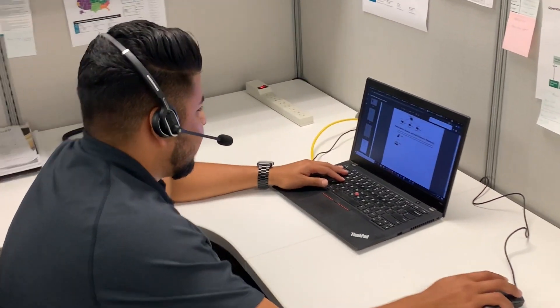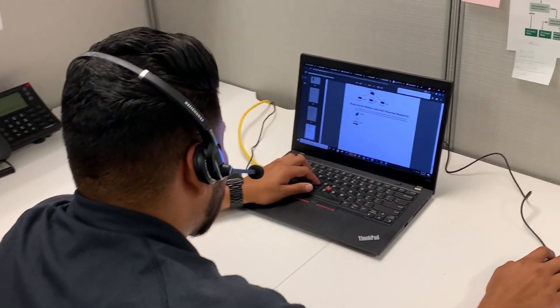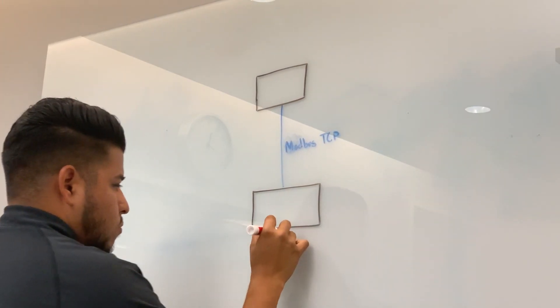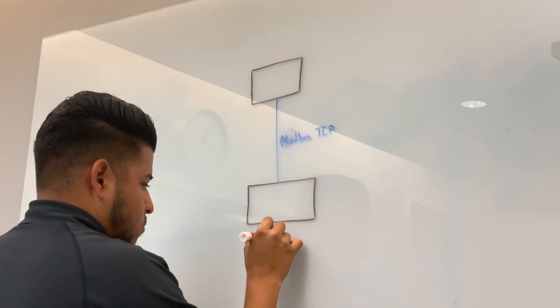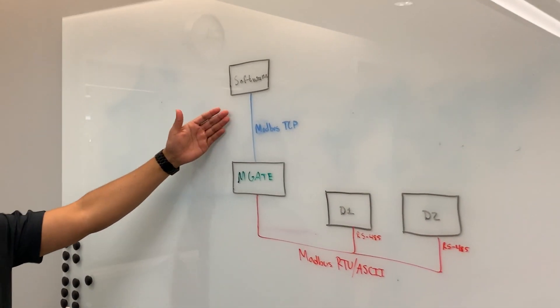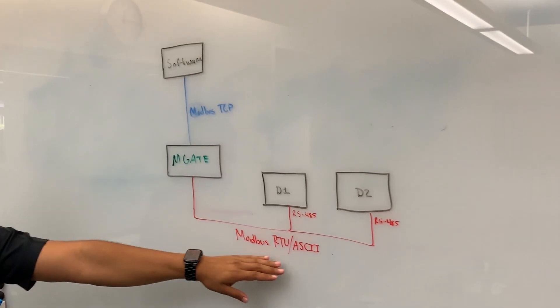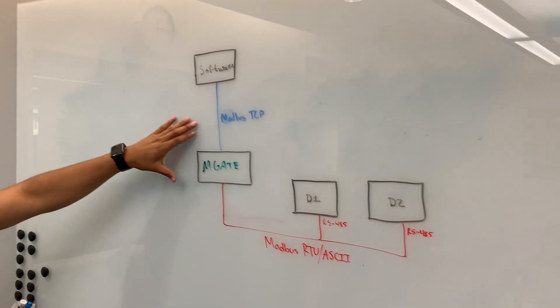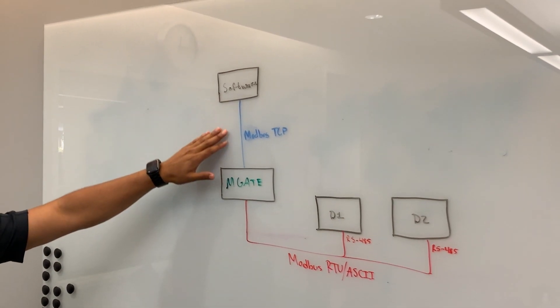The customer was looking for a Modbus gateway to replace because his original one was discontinued by its manufacturer. The protocols being converted were Modbus TCP to Modbus RTU. On the TCP side he has software collecting data, and on the Modbus RTU side were all the serial devices he was collecting data from.